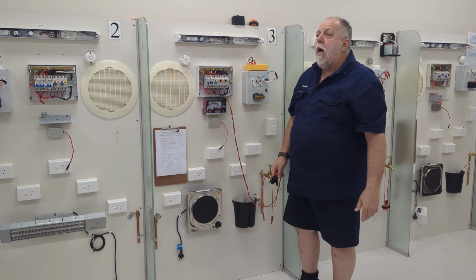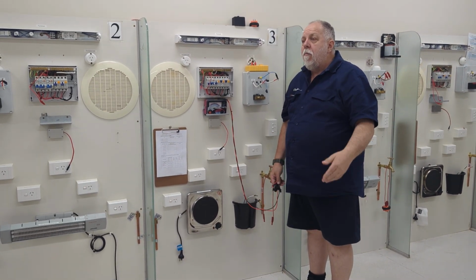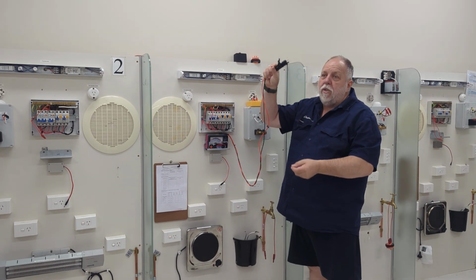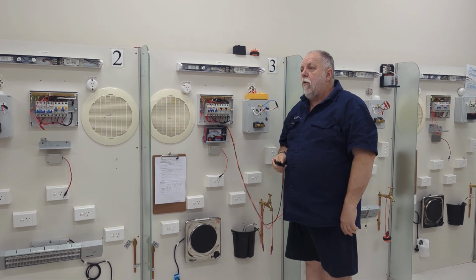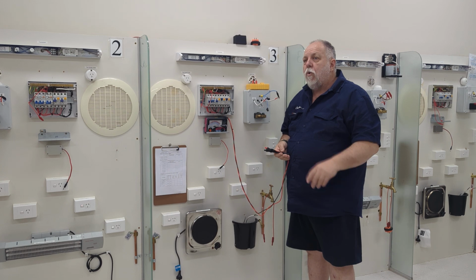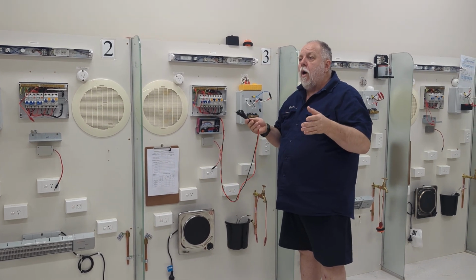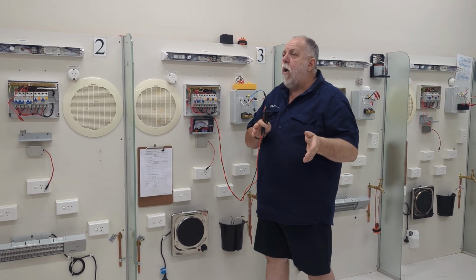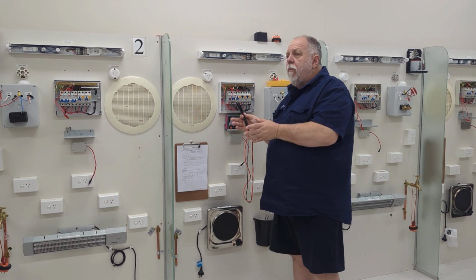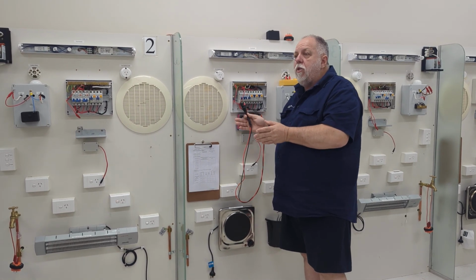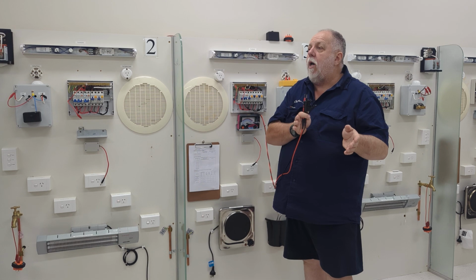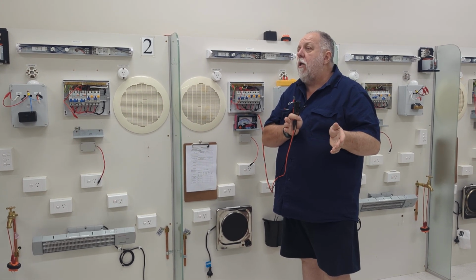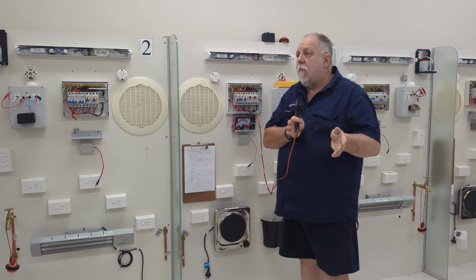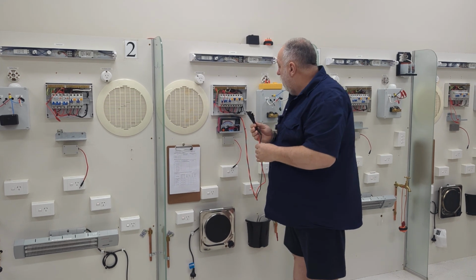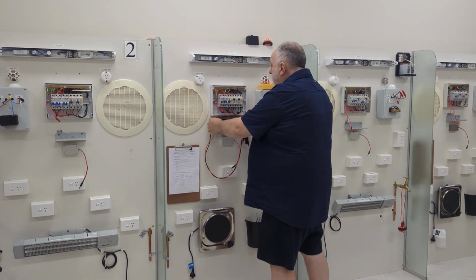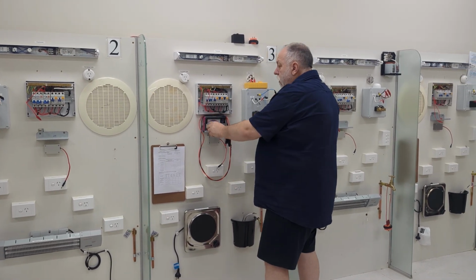I take that value back and I have a look at table 8.2, like we did when we measured the resistance of the earths, and then we added to the active value. Do you understand what I'm getting at? So it's called the RPHE value. The difference with 8.1 to 8.2: in 8.2 we're looking for the resistances of the circuit. 8.1 is when the circuit's got 240 volt on it and it's under load. Does that make sense? We all got that? All good. Do I need to explain any more on that? Are we all hunky-dory? Yes?